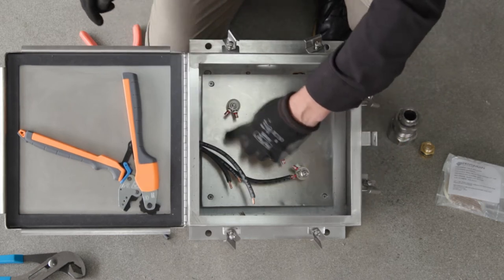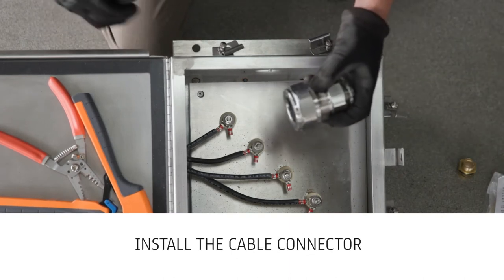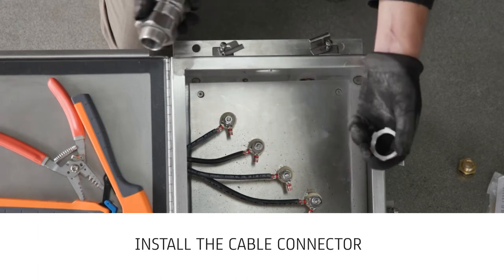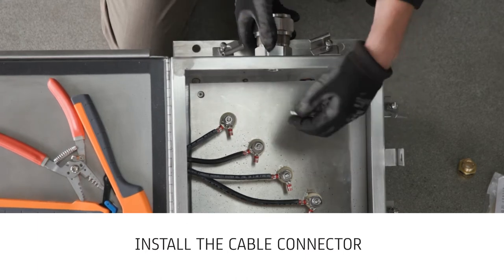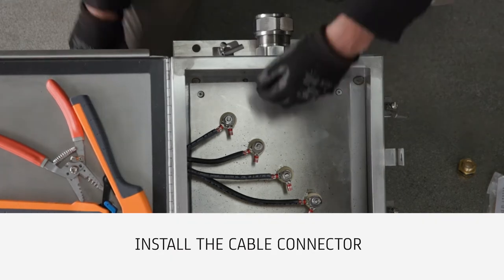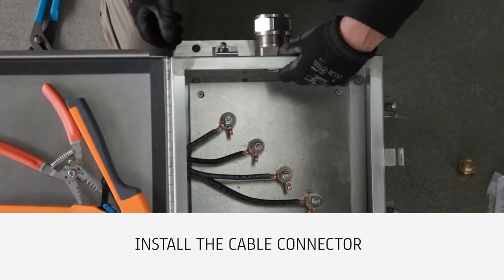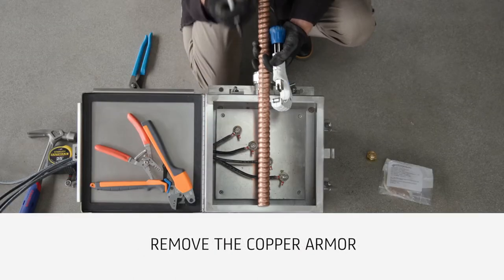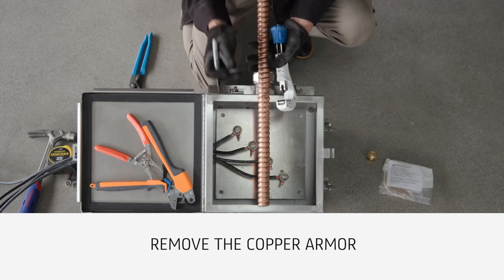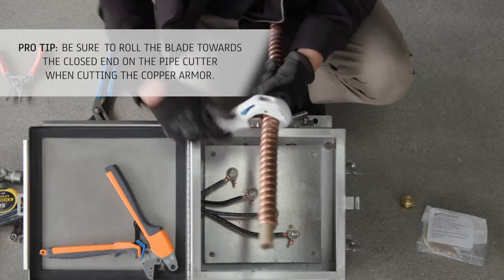Complete the remaining splices. Install the Remke Powertech metal clad cable connector and secure using a stainless steel locking nut. Remove the copper armor from the cable using a pipe cutter, being careful not to cut into the inner binder jacket. It is recommended to have the cable the length of the enclosure available for terminating.